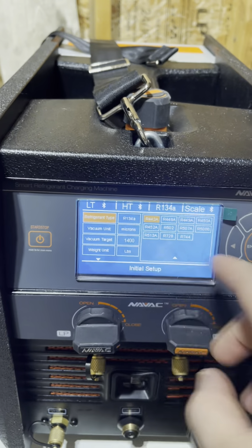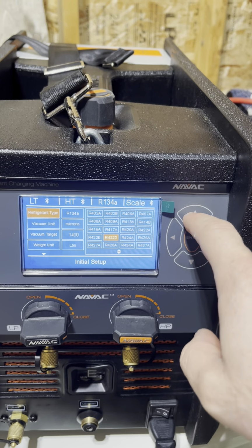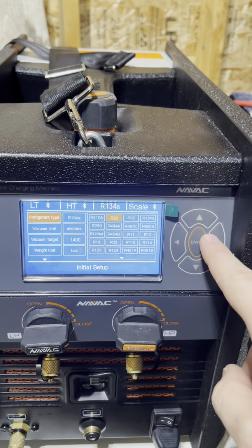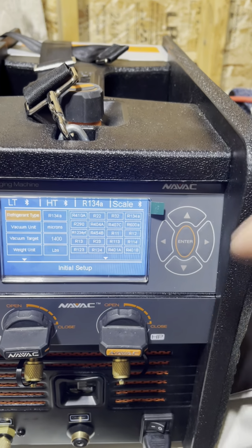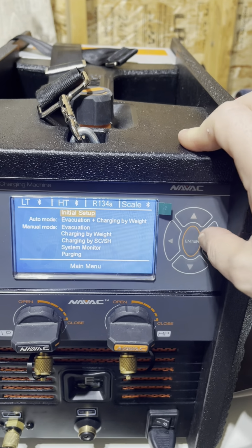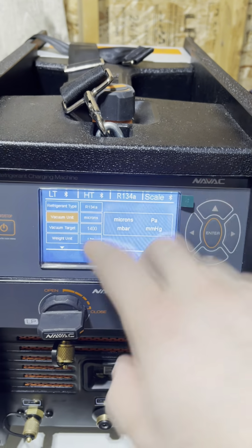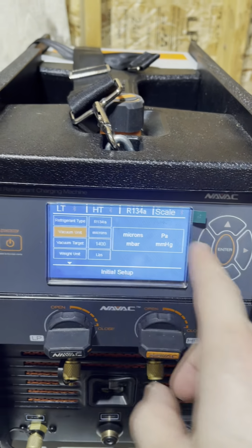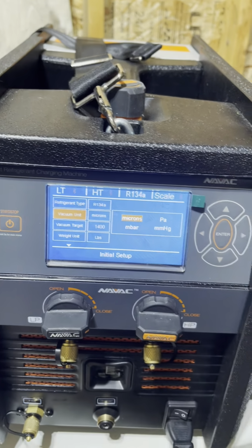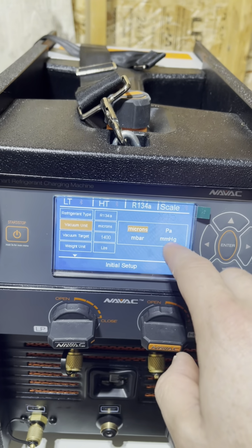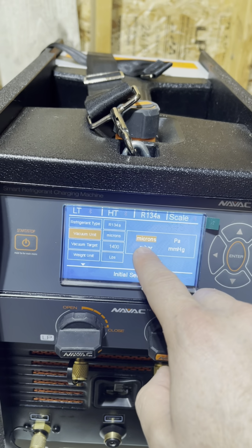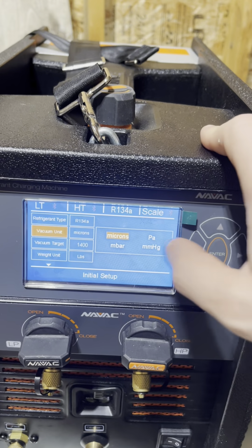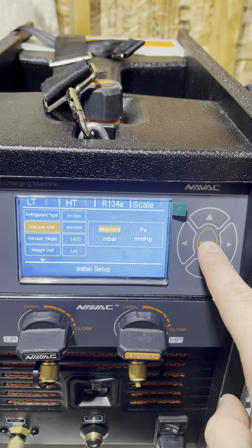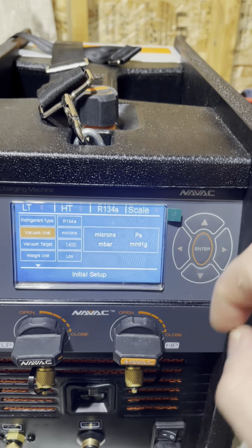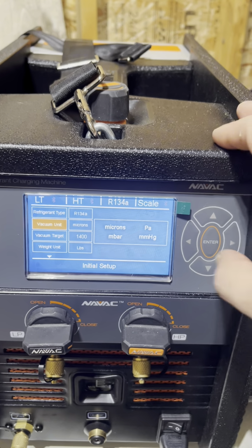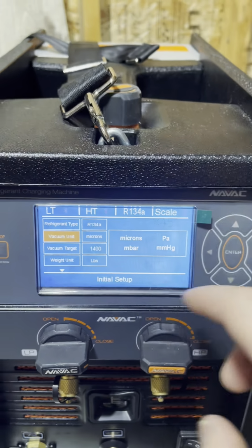So when you just start, you have to select the refrigerant that you use. Let's say for this demonstration, I'm going to use R134A. Then you have to select the vacuum type. In our case, we use microns. So you have 3 more options. We don't use these options. I personally use just microns. And then you select enter. Once you do enter, it will save the setting in the system.